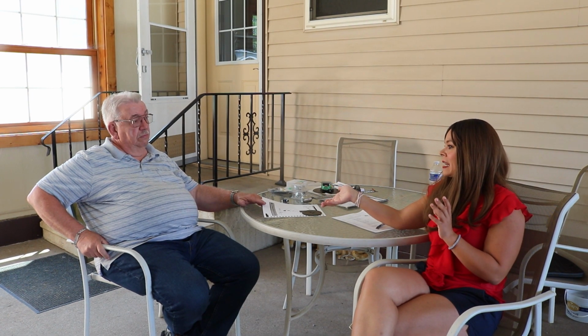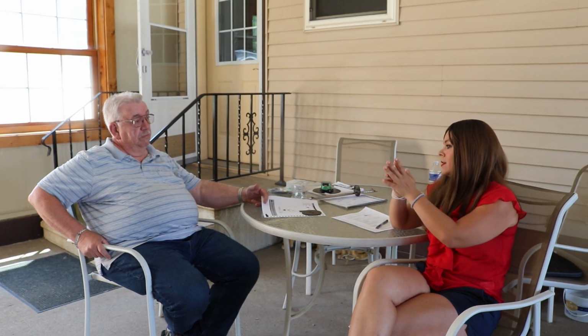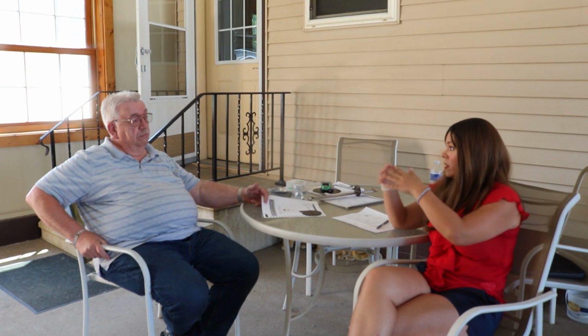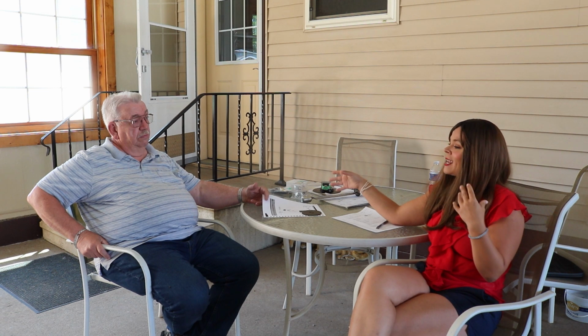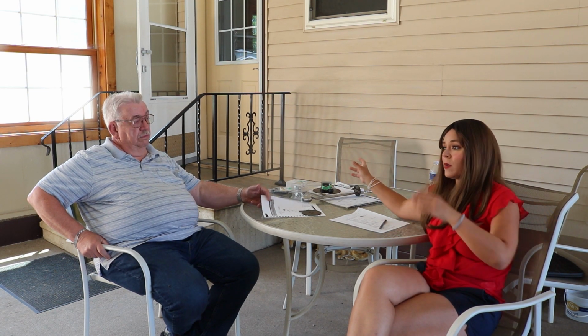And then if we sized way up, let's say we're like a 400,000 BTU range, maybe more commercial, and, well, let's say we're actually heating 2 buildings, okay? Like a home and a shop, and we've got, at that point, a 200-foot run, combined. What kind of sizing would we be looking at? And let's say the shop is water to air, but maybe the house is in-floor. The house would use maybe a little smaller pump.